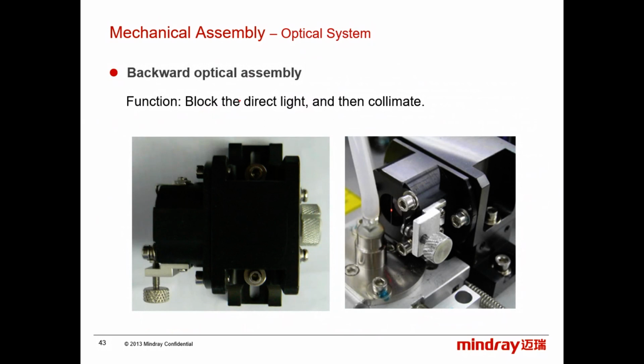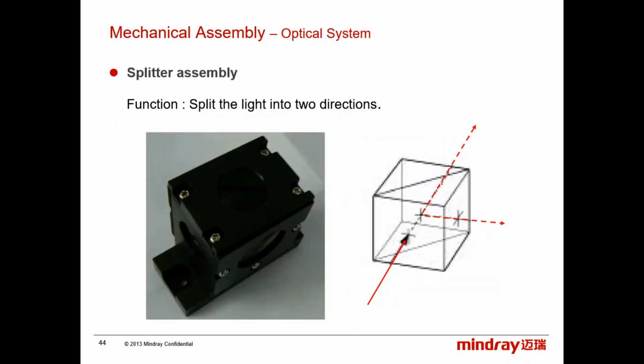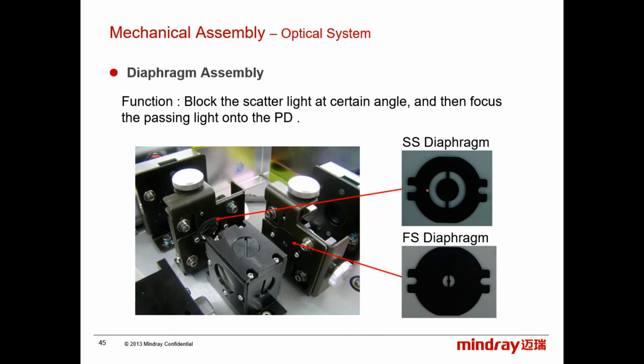This is the backward. Okay, block the direct light and then collimate. This is the splitter. We split the light. This is the diaphragm. Okay, this is just to reduce the incident light. Okay, block the scatter light at certain angle and then focus the passing light into the photodiode assembly.